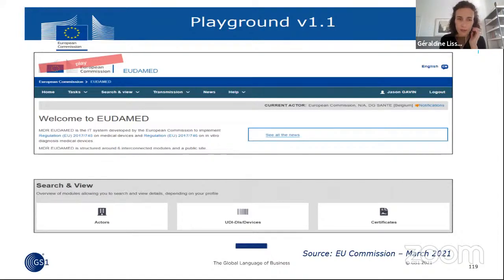So you'll see here, what is important is that you really have these different modules. So today, the actor registration module is live, and that's a prerequisite. So if you want to register a device, you first must register yourself as one of the actors. And not all types of economic operator are able to register themselves as an actor. You have to be a manufacturer, authorized representative, importer, or a packager of kits and procedure packs. Once you've done so, you receive a number that is randomly generated by EUDAMED, so it's not GS1, called the SRN. With this number, you will be able to register your devices. You will also be able to download or upload your certificates and so on and so on. So really, the first step: register yourself as an operator.